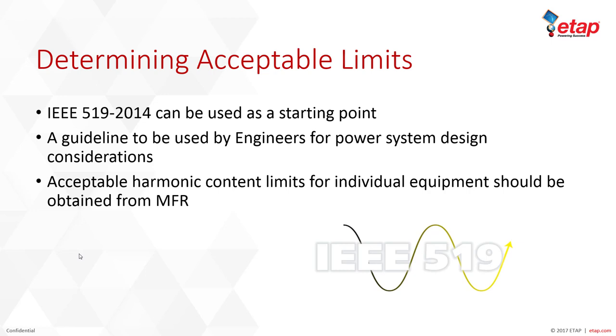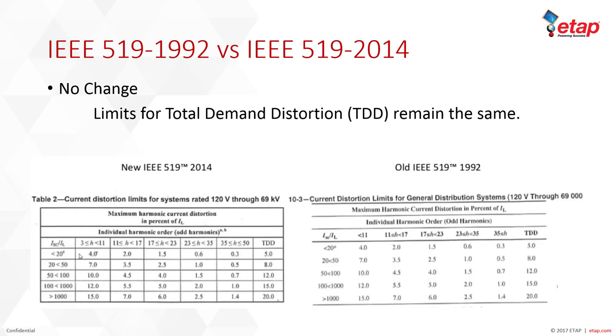Let's look at the differences between IEEE 519-1992 versus 2014. The 1992 standard is currently implemented in software like ETAP, and the 2014 update will be released in the next version. Starting with the limits for total demand distortion — the old Table 10-3 from 1992 corresponds to Table 2 in the 2014 standard — these limits remain the same, so nothing has changed there.